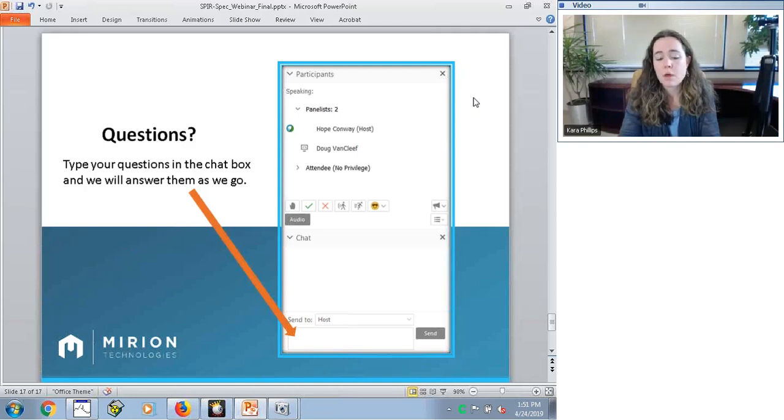In longer term, what we typically recommend is using a cesium-137 source or other check source. And the auto-calibration option is going to work through a series of routines where the user will specify which kind of nuclide they are looking at. So for instance, cesium-137. And then the software will adjust the gain to bring the expected energy calibration right back to where it should be. And so that's something that we recommend doing really in the beginning of any given measurement campaign. And it works pretty well.